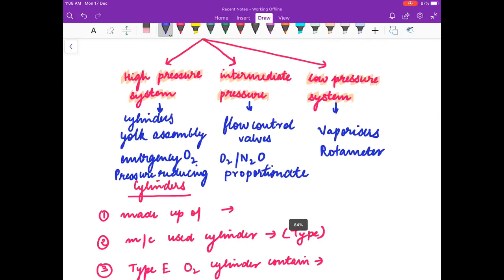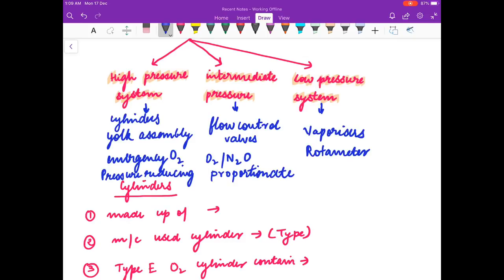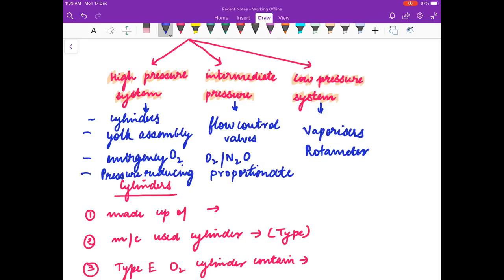Friends, learn this by heart: the high pressure system includes cylinders, yoke assembly, emergency oxygen flush, and pressure reducing valves. The intermediate pressure system includes flow control valves and oxygen-nitrous oxide proportionate devices. The low pressure system includes vaporizers and rotameters.